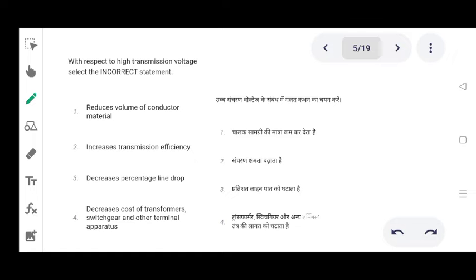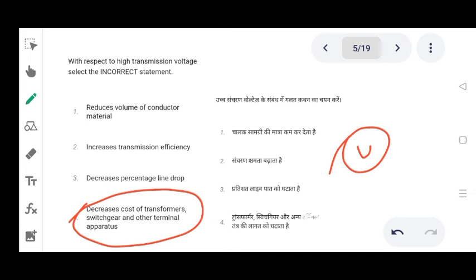Next one. With respect to high transmission voltage, select the incorrect statement. Option 1, reduce volume of conductor material; 2, increase transmission efficiency; 3, decrease percentage line drop; 4, decrease cost of transformer, switchgear and other apparatus. Correct answer is decrease cost of transformer, switchgear and other terminal apparatus, option 4.